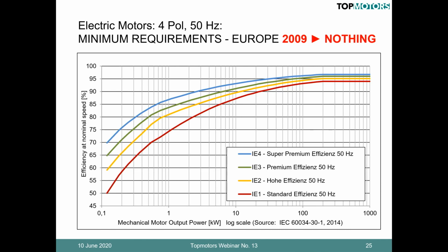The IEC standard, which is the baseline for these 4 efficiency classes, has been published. The standard is called IEC 60034-30-1, published in 2014, but the predecessor was already published. And here we show 4 efficiency classes. The red one, IE1, is the standard efficiency. The yellow one, IE2, is the high efficiency. And the green one, IE3, is the premium efficiency. And also the IE4 is already determined now. It's called the super premium efficiency.